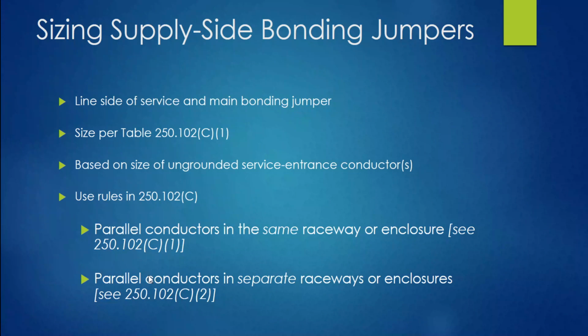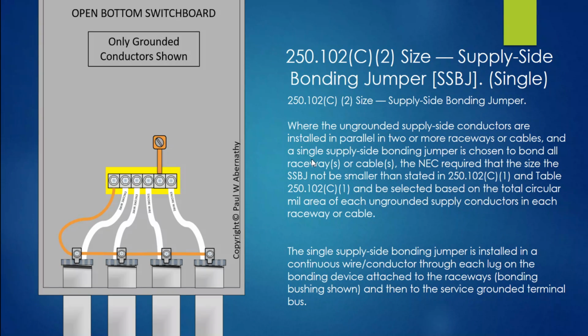But what happens if we have multiple raceways, two or more, and we're paralleling it out? That was our example where we showed three coming into that piece of equipment. Then we're going to use 250.102(C)(2) for that application. So let's look at the application where I've got multiple raceways coming in. In this case, it's an open bottom switchgear. It comes through the bottom, and it's sitting on a slab, and these come up through the slab. Probably didn't show that real well, but anyway, they're open bottom.